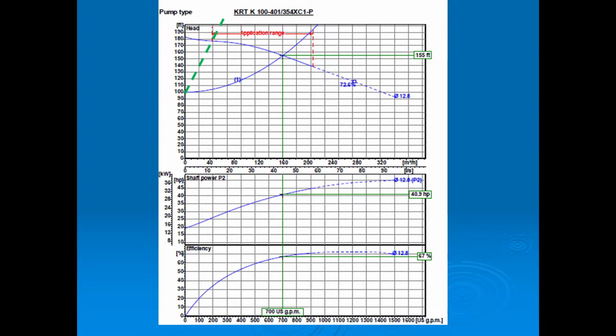It just doesn't work. Therefore, you want to make sure you have something that's going to operate easily and well, regardless of the conditions. You never want to operate to the left of that curve. You don't even really want to get close to it if you don't have to. Usually, conditions of lower flow and higher head are areas you've got to be careful of, like 50 to 100 gallons a minute at 75 to 100 or 150 feet of head. Those are conditions you've got to be really careful of.